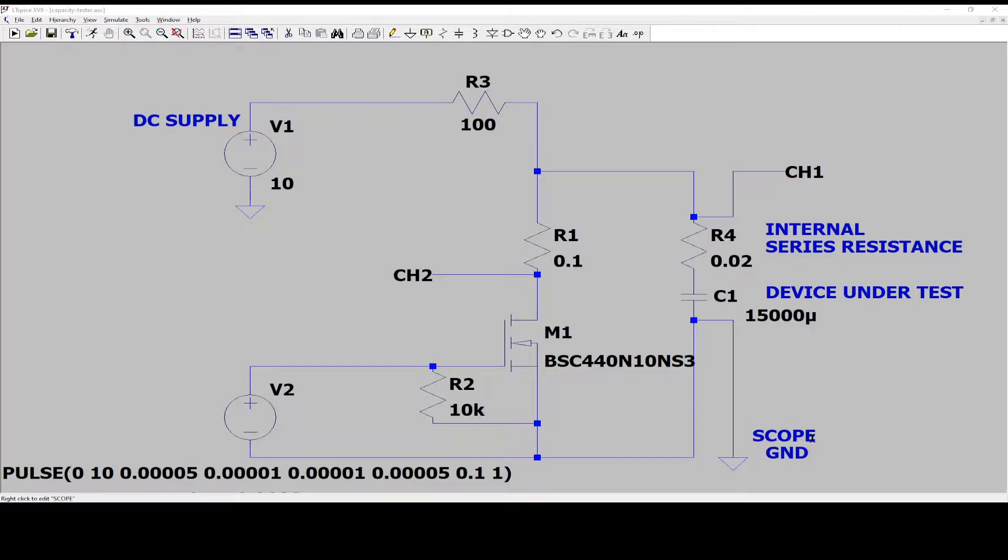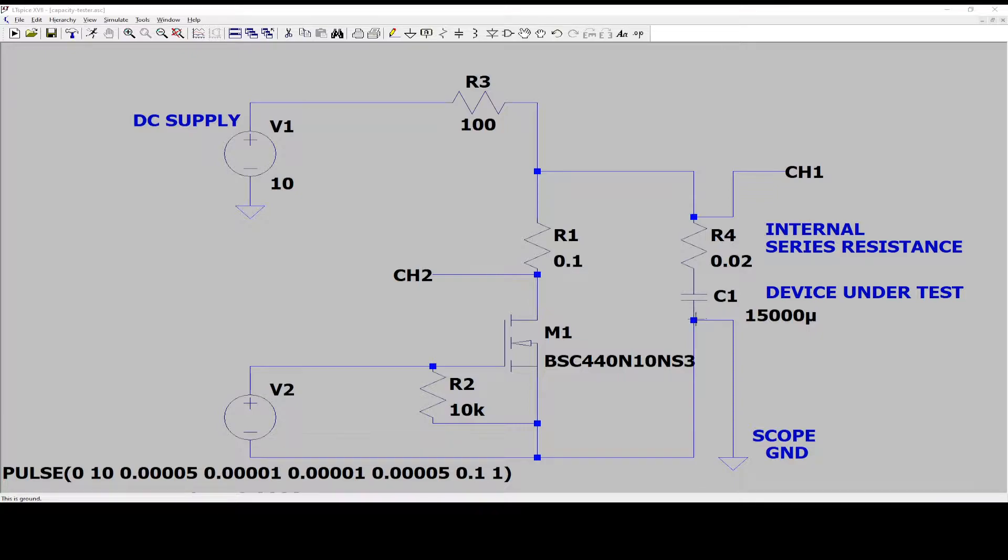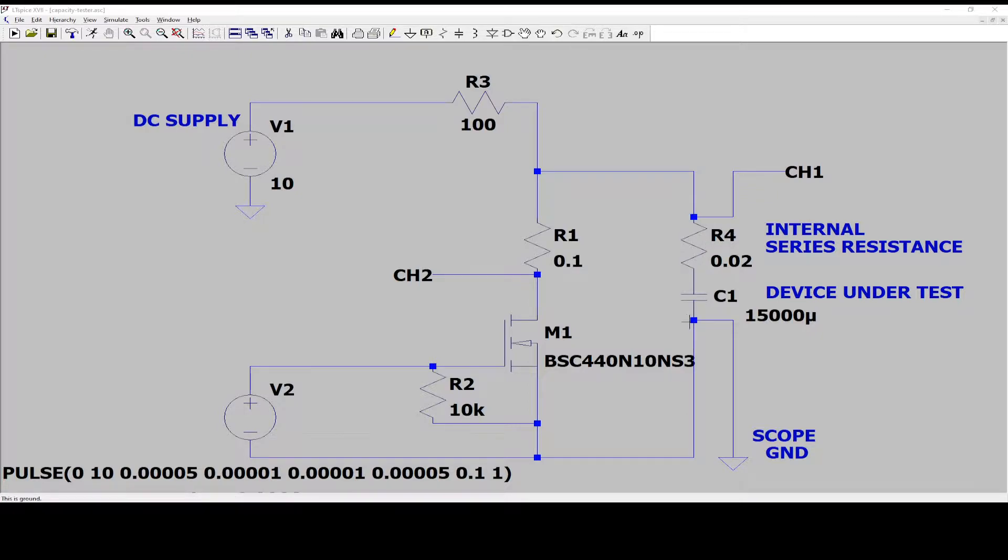So your scope, your two scope probes, you connect as close as possible to the ground terminal of your capacitor. That means because we want to measure the voltage drop when we are pulling a lot of current out of the capacitor. So this is the point where we measure.